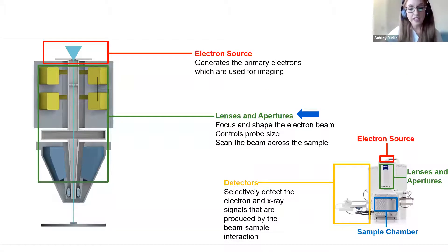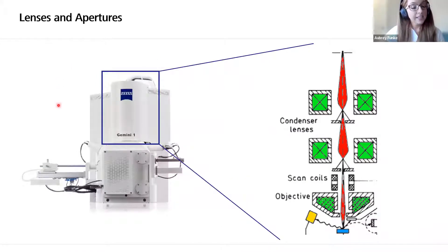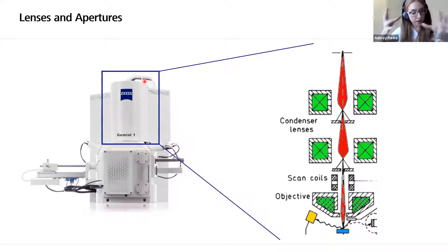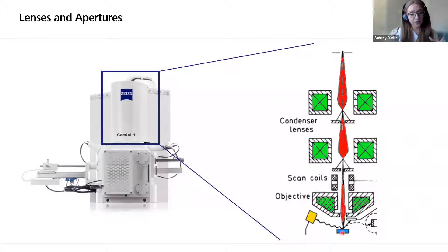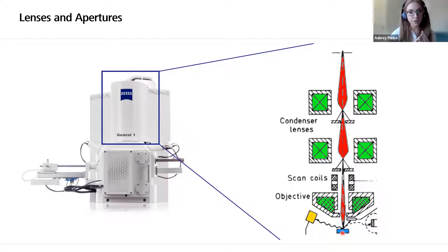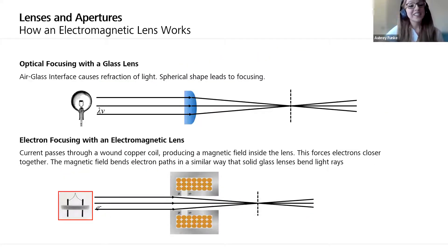Now that we know where the electrons come from, we can move on to the electromagnetic lenses and how they are used to form and focus that beam. The lenses are located in the column and are used to reduce the diameter of the beam — you want a spot as small as you can possibly get. In that very last lens, there are scan coils that take that beam and move it across the sample in that raster pattern. The lens system consists of condenser lenses, objective lenses, apertures, and those scanning coils.